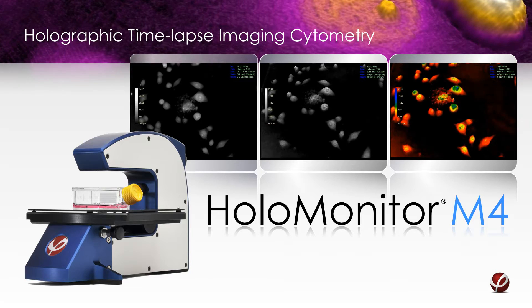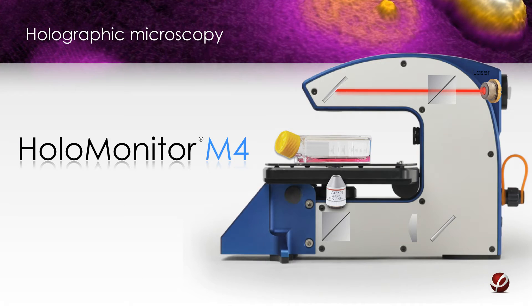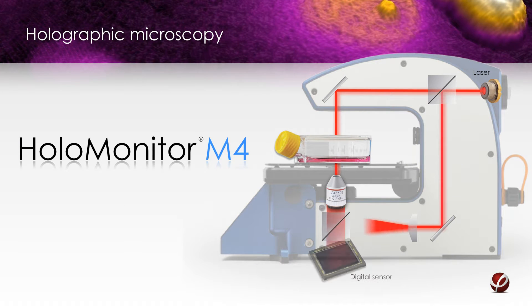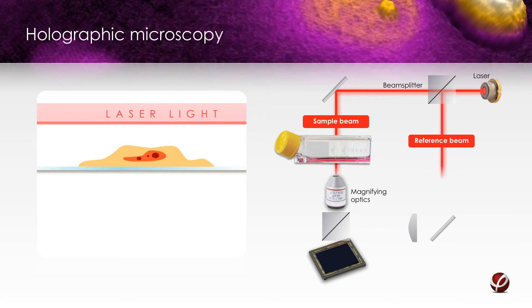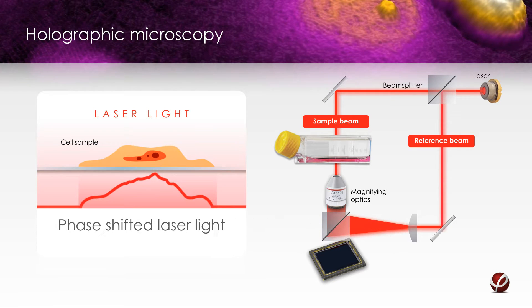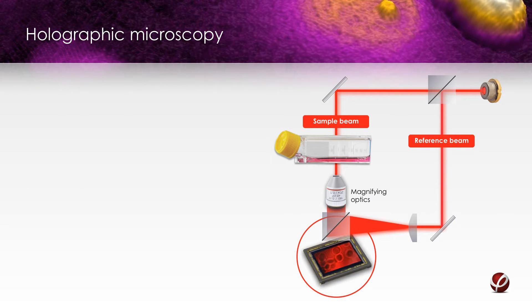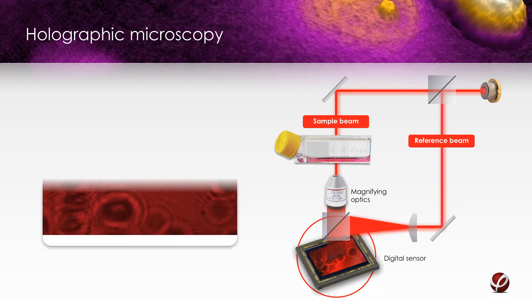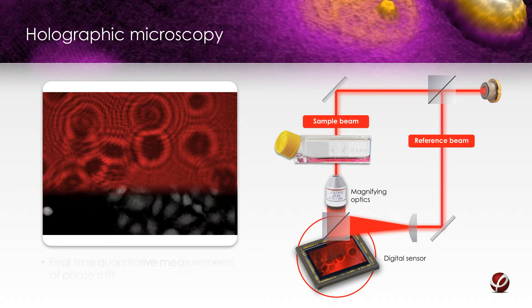HoloMonitor M4 utilizes the principle of holographic microscopy. A low-power laser beam is split into two beams, one illuminating the sample and the other providing a reference beam. Laser light passing through the sample is affected by intracellular structures, causing a phase shift of the illuminating light. Once combined, the two beams create an interference pattern that is recorded by a digital image sensor. The interference pattern is then processed computationally to produce a holographic image.